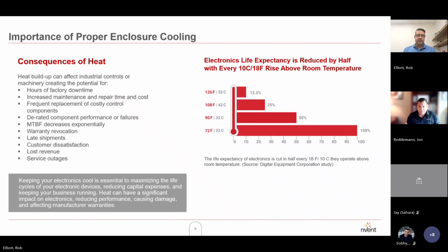So if we have a drive that's rated at 50 C and we're operating it at that condition consistently, we won't get that, let's say, expected 10-year lifespan. We'll get about 2.5 years off of that drive, right? So managing the internal heat load and the temperature inside of an enclosure is really critical for the overall life expectancy of those systems.